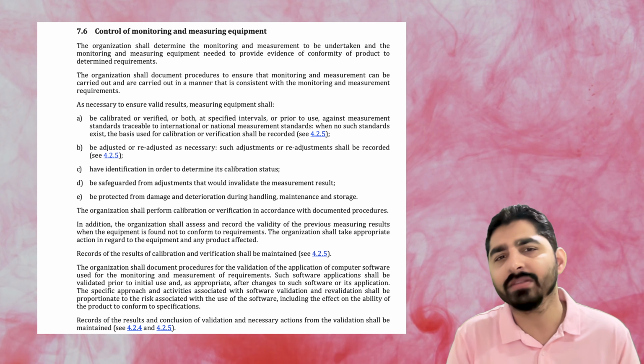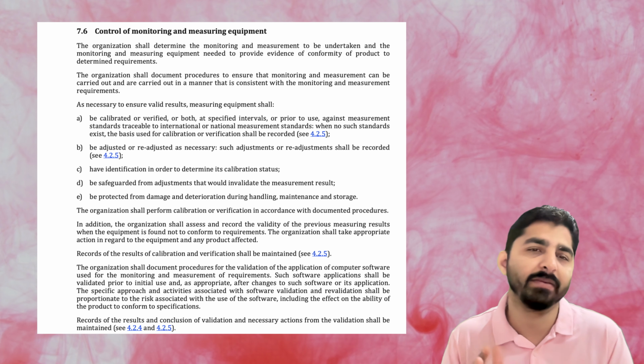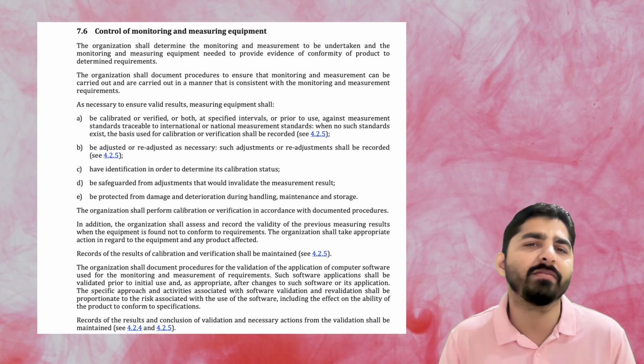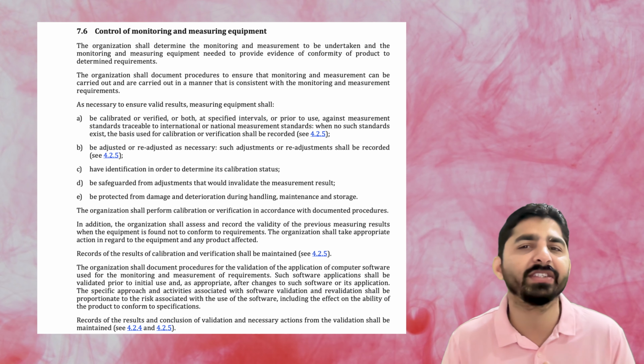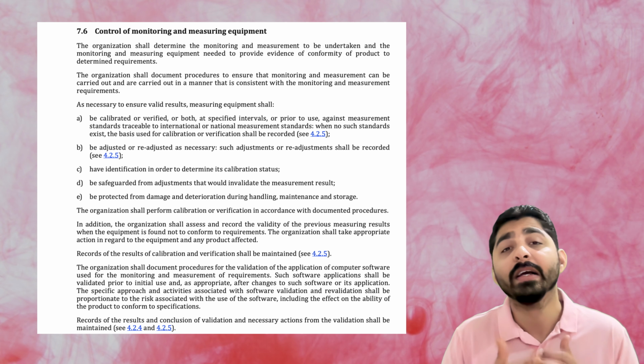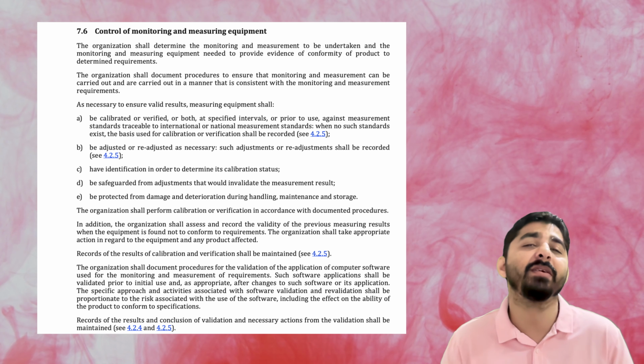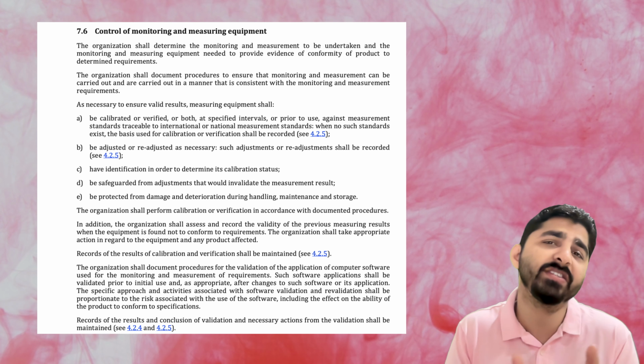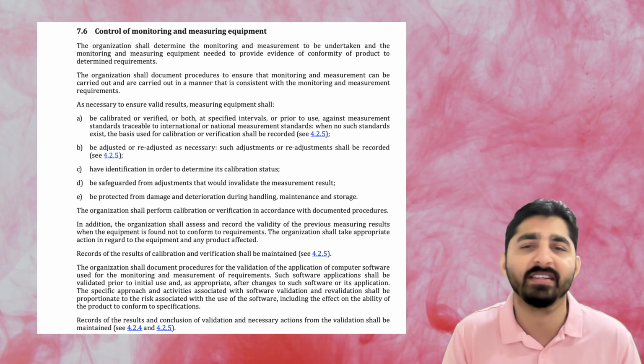The record of the result of the calibration and verification shall be maintained. The organization shall have a documented procedure in place for the validation of application of computer software used for the monitoring and measurement of the requirement. Let's say we have deep freezers, refrigerators, and humidity chambers installed across our facility, right? And we have an inbuilt system of taking data at a particular frequency interval, let's say temperature data or RH data.